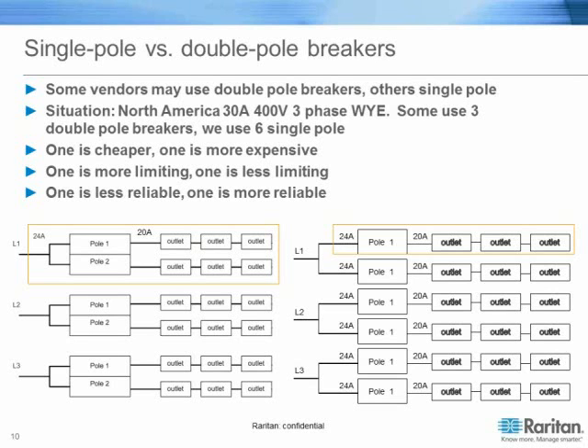You start plugging everything in, running the microwave and the coffee maker, you're going to trip a breaker. In this example, we've seen customers out there with the lower end PDUs say, hey, I'm just going to plug as much stuff in, and surprise, I just tripped a breaker. Again, that's not good to do on a data center level, and it's not good to do on a rack level. We want to make sure those servers are brought down gracefully.